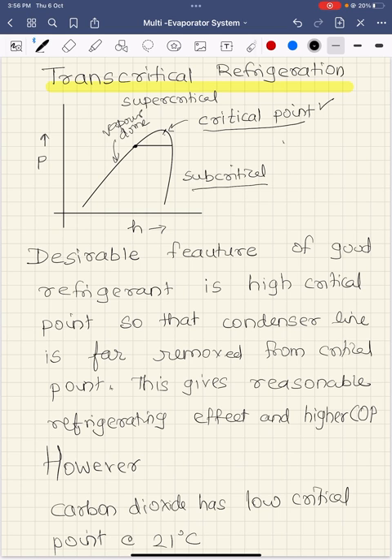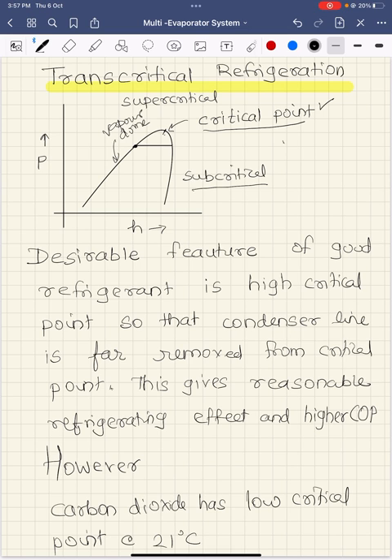Let us understand the transcritical refrigeration cycle by referring to a commonly used refrigerant in the transcritical cycle, which is carbon dioxide. Carbon dioxide, also known as R744, is a natural refrigerant. The interest in the transcritical cycle stems from the use of carbon dioxide. We all know that the commonly used refrigerants are hydrocarbons or hydrocarbon derivatives — HCFCs are nowadays used. All these hydrofluorocarbons and chlorofluorocarbons have the characteristic that their critical point is high.